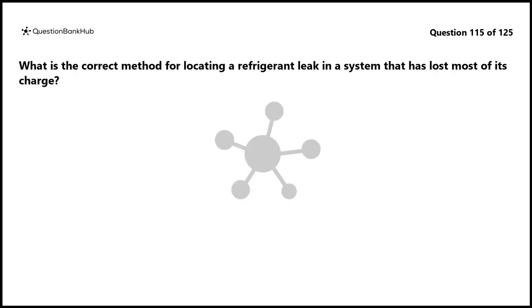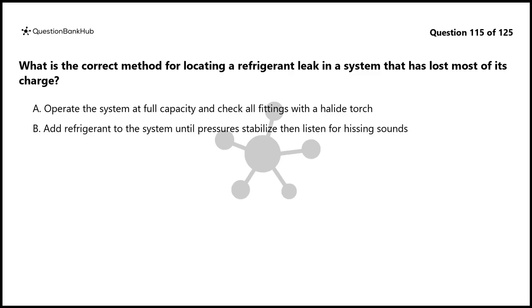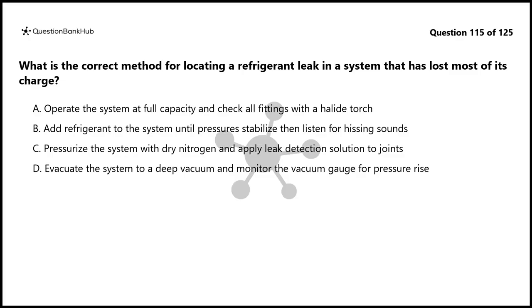Question 115. What is the correct method for locating a refrigerant leak in a system that has lost most of its charge? A. Operate the system at full capacity and check all fittings with a halide torch. B. Add refrigerant to the system until pressures stabilize, then listen for hissing sounds. C. Pressurize the system with dry nitrogen and apply leak detection solution to joints. D. Evacuate the system to a deep vacuum and monitor the vacuum gauge for pressure rise.